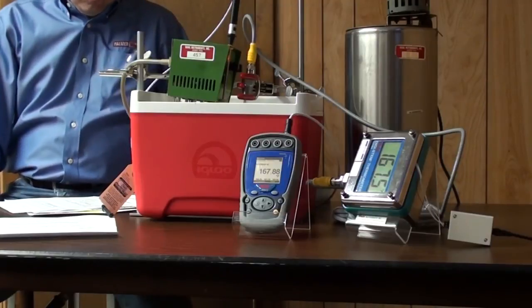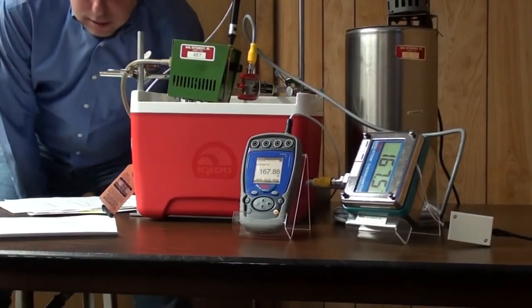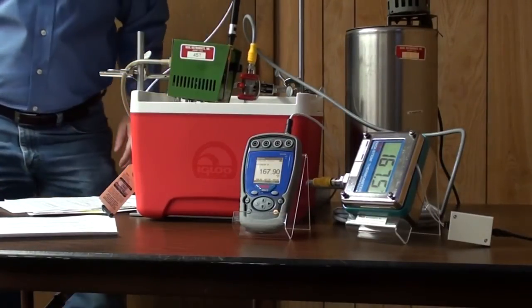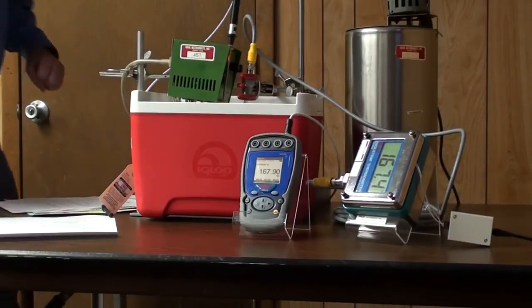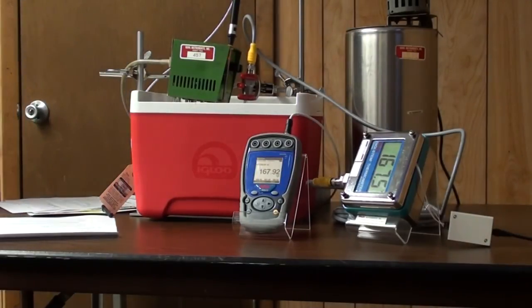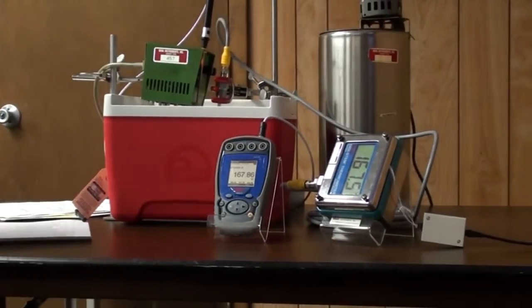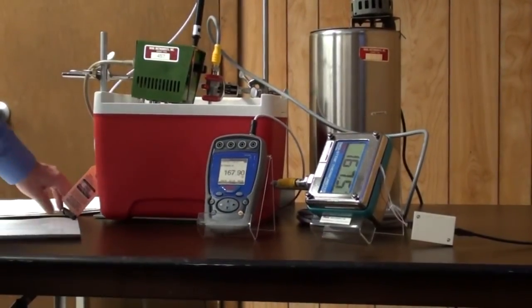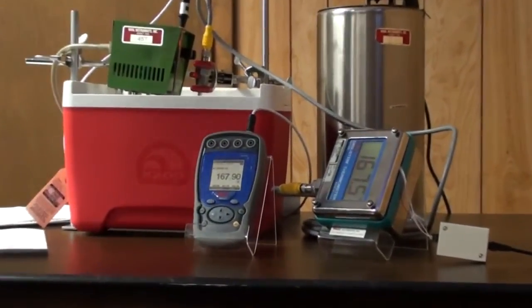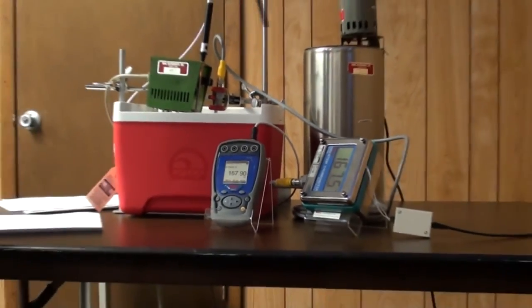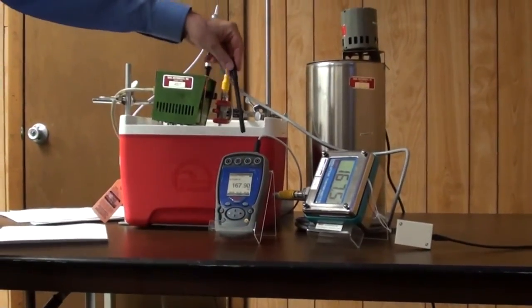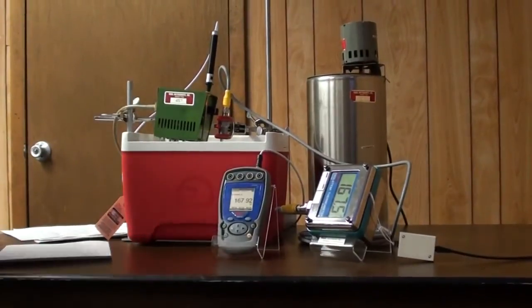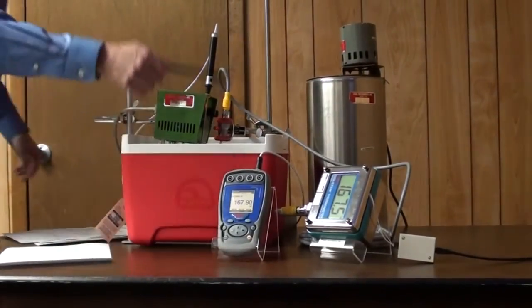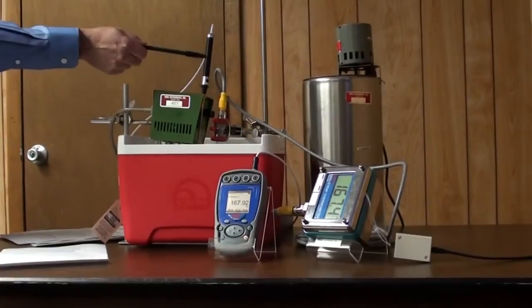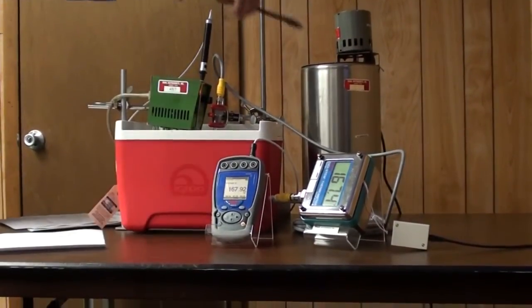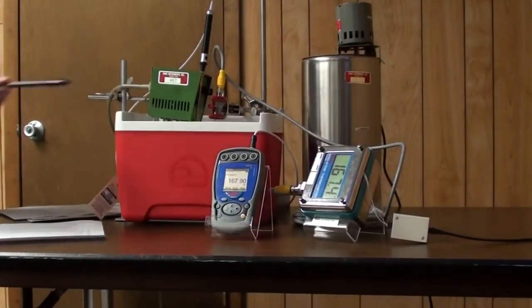So this is our DST Cal. Before we get to that, I'm going to step around here. I can't tell if I'm in the image or not because I can't see it from here, but that's all right. Basically what we have is the Digi-Stem we're going to calibrate, and this one has a remote cable on it. This is our standard instrument, a TM612, and it's got a 4-wire RTD probe up to here. I do have an ice bath sitting back here. We will be using that.